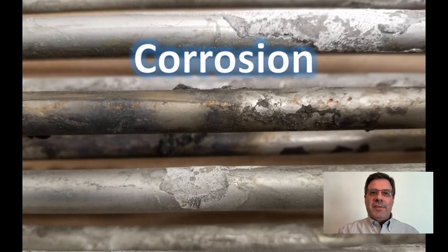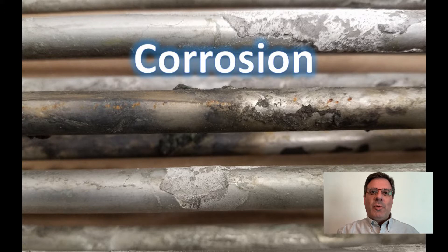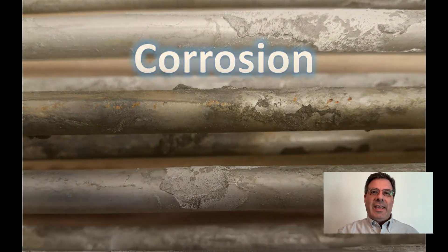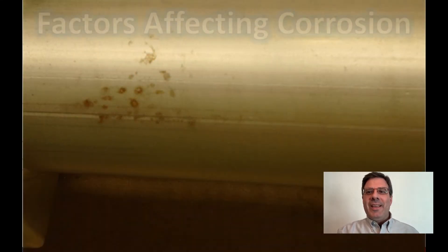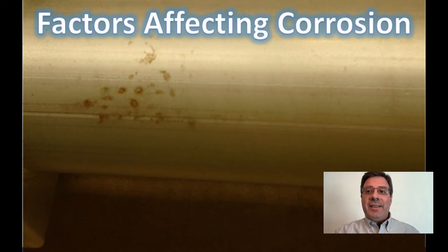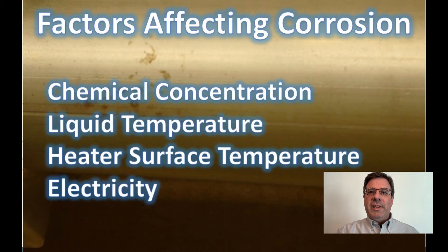The first most common cause of failure is corrosion. This means that either the process chemical in the tank or some drag-in chemical from a previous tank is reacting with the heater surface. The rate of corrosion is affected by many factors, including the concentration of the chemicals, the operating temperature of the bath, the surface temperature of the heaters, and the presence of any stray electrical currents.